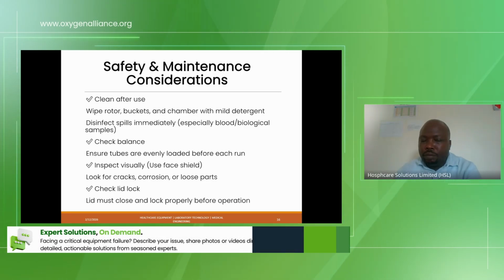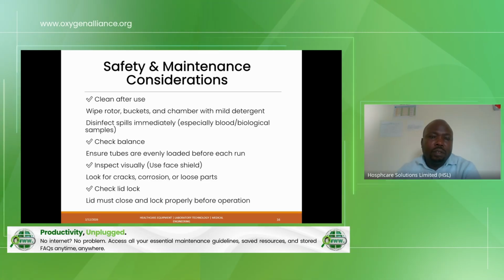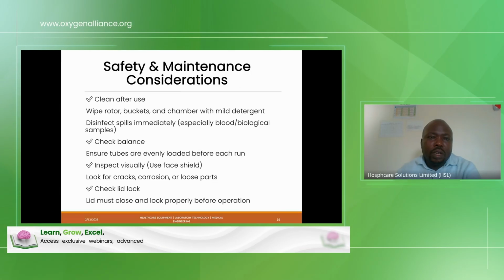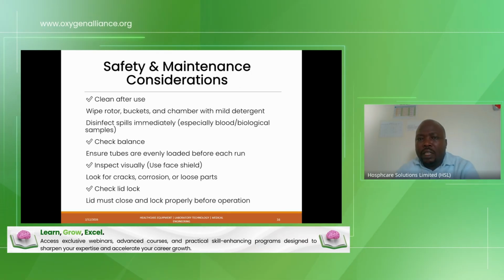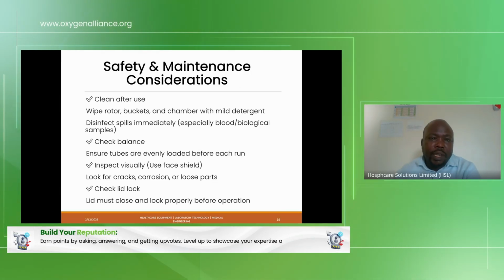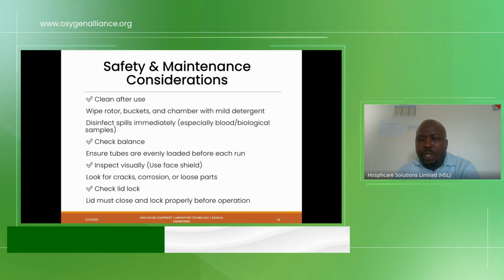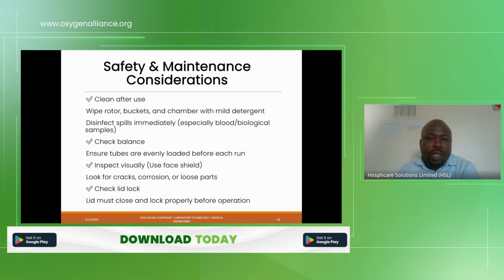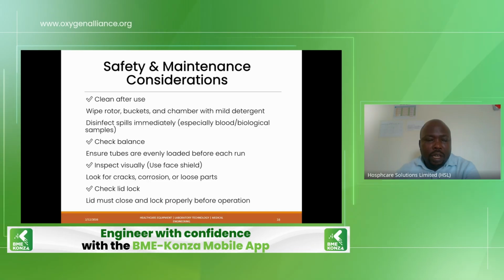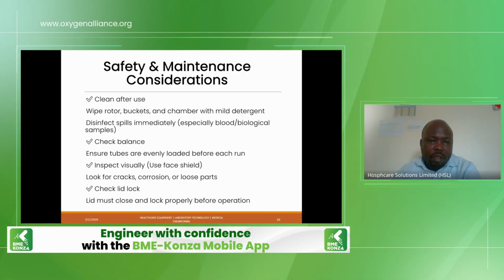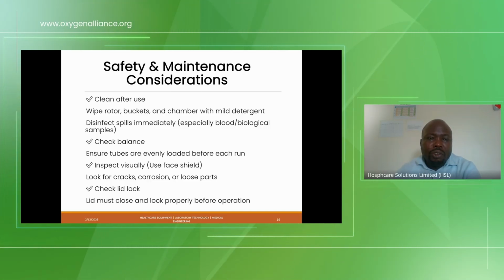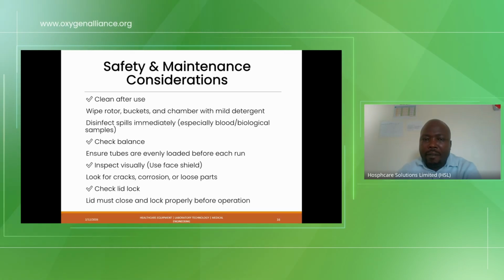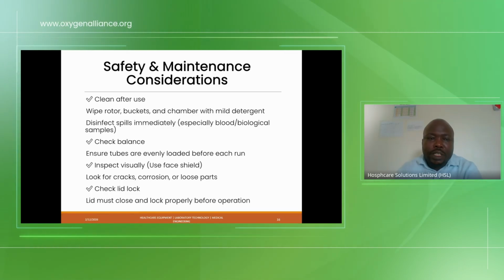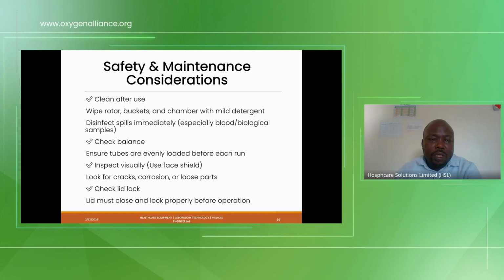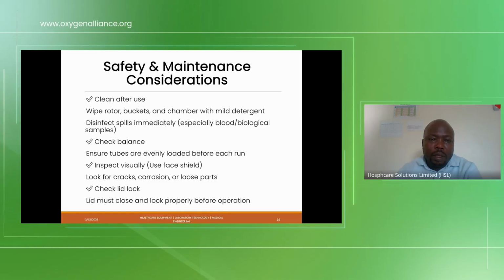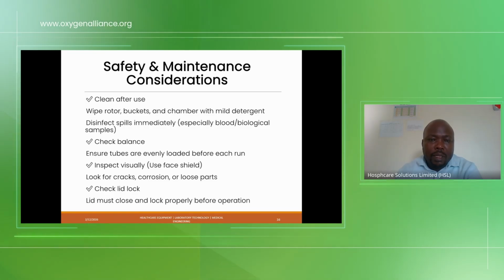We have to clean the stainless steel chamber after every use. You wipe the rotor, buckets, and chamber with mild detergent, and you disinfect any spillage immediately, especially blood and biological samples that can create a biological hazard to the surrounding environment. We check balance and ensure tubes are evenly loaded before each run. There's a reason for this. We'll see the importance of balanced sampling.